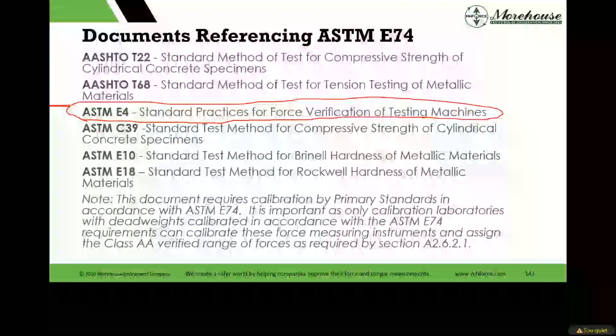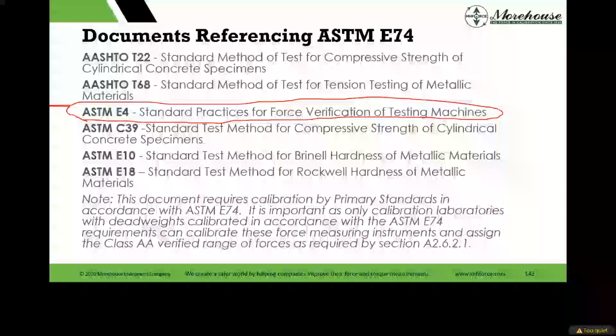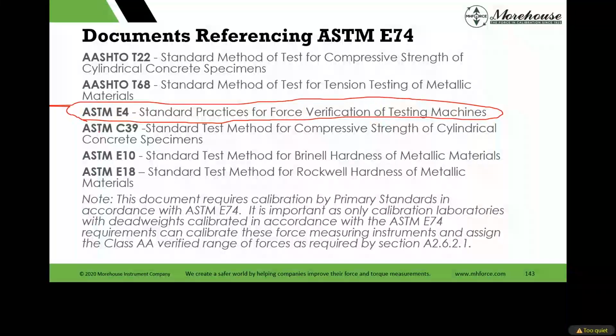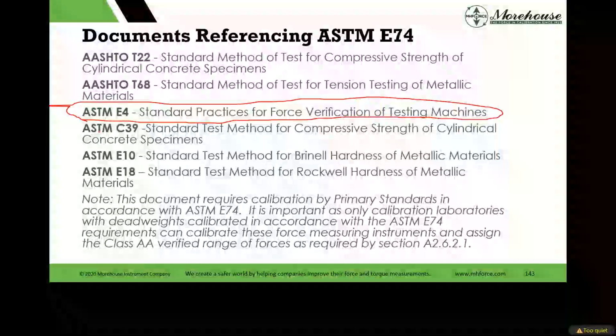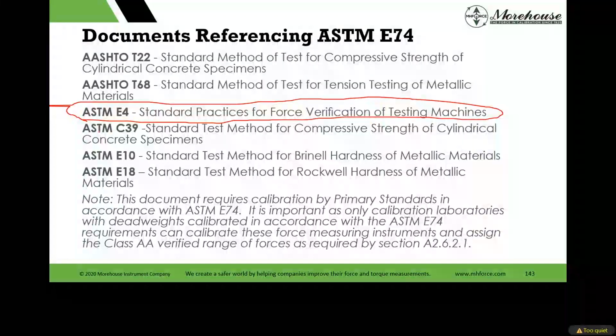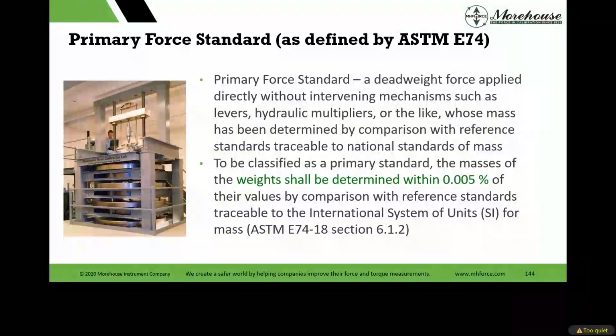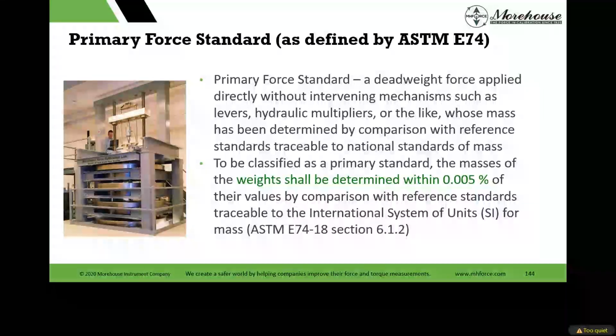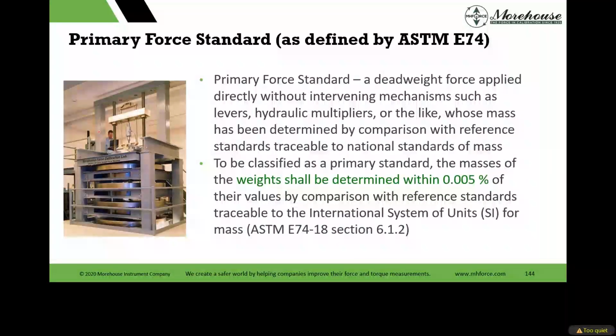There's a line in there under the verification about having to have devices calibrated with a class AA, meaning primary standards, and E18 has that same line. So if you are doing hardness testers or calibrating to E10 or E18, E74 is going to have some reference. Of course, it has reference to E439 and the other ones. What E74 basically says is a primary standard is this. It's a deadweight force directly applied without mechanism, levers, or multipliers, and whose mass is determined with reference standards traceable to national standards of mass.